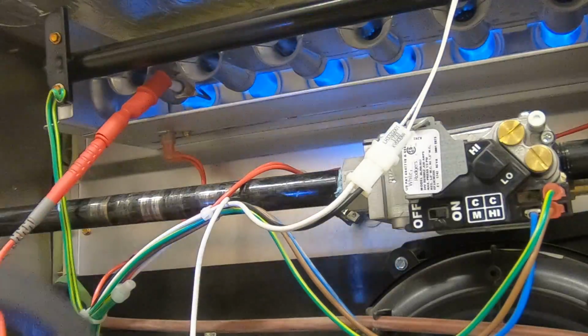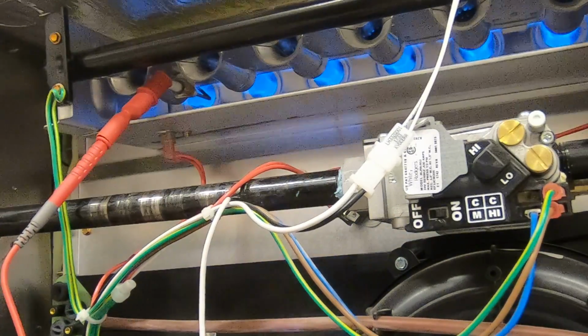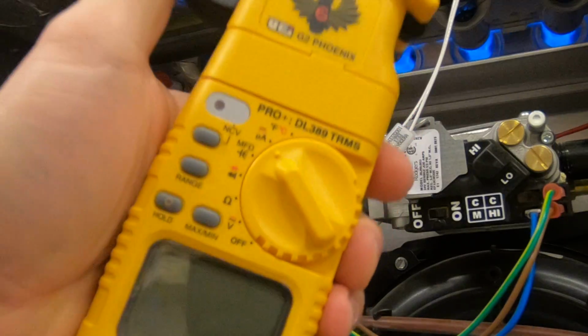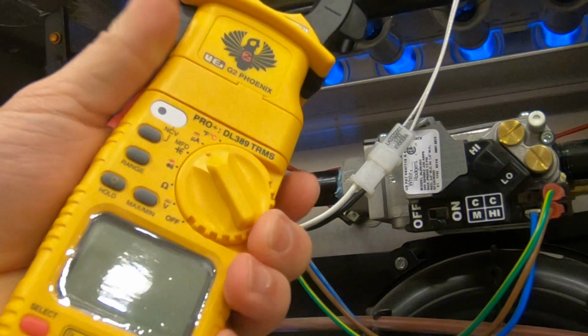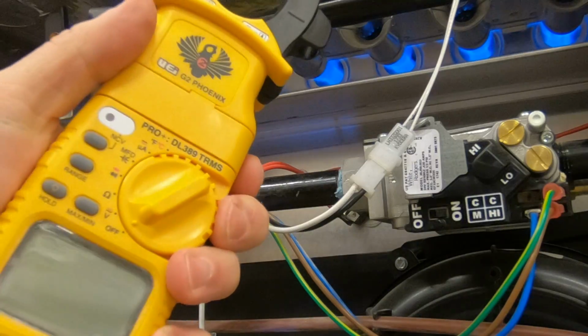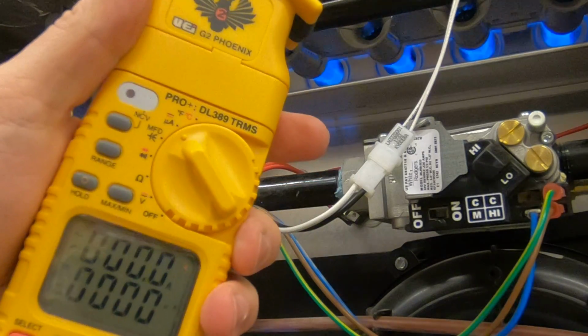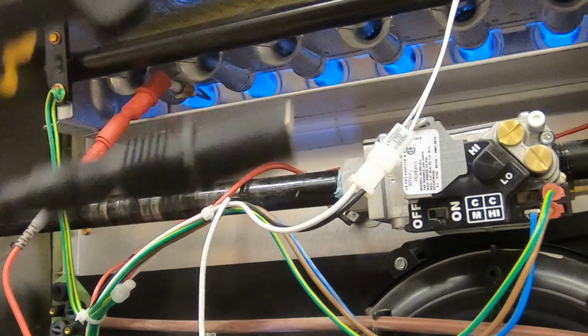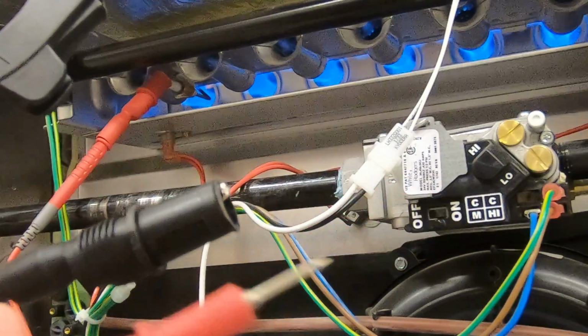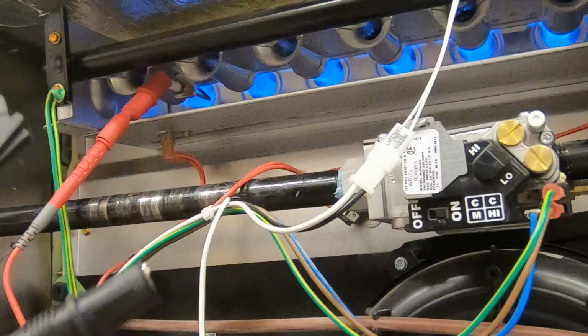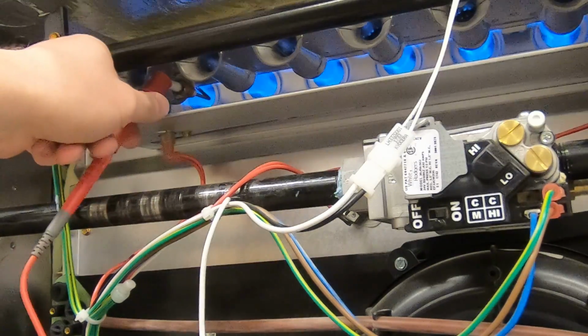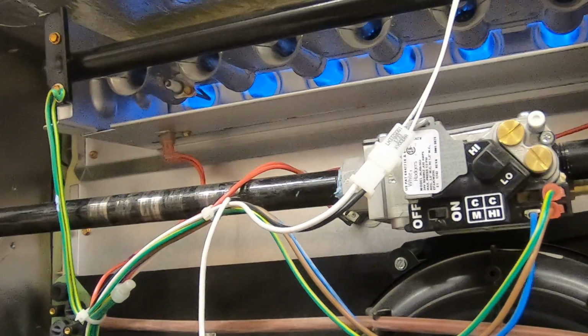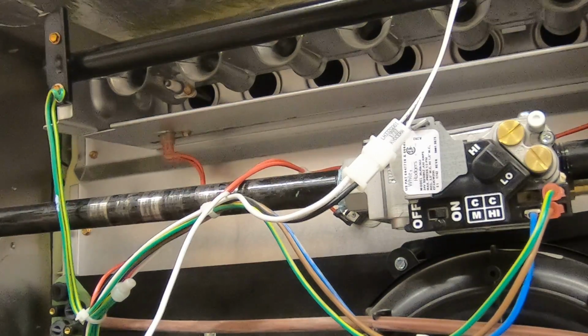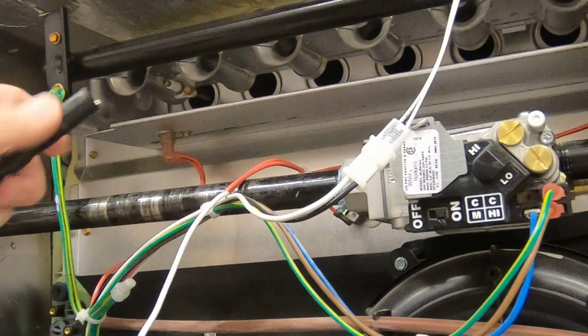So while we're in this, I'll show you the same thing on another meter we have here, the DL389. So if you just so happen to be using this meter currently, you turn it to micro amps. Same thing, probe on one end. It doesn't really matter where the probe is, the alligator clip. And on this side of your other probe, we're just going to unhook this. And when we unhook it, you'll see the flame go out. So the machine thinks that it just stopped seeing flame on its sensor, so it just turned off.